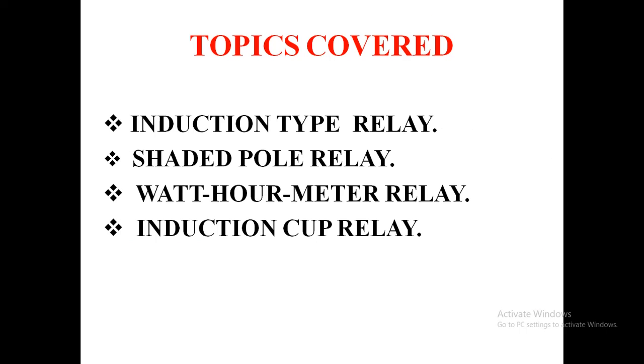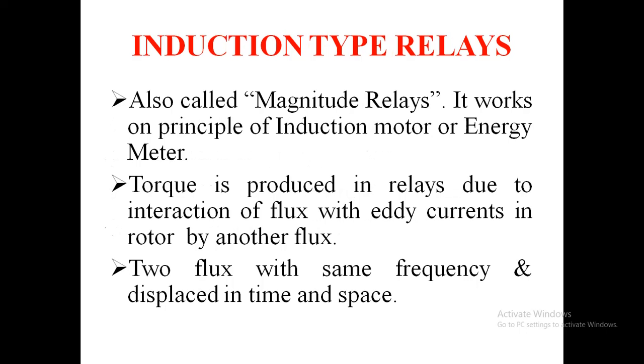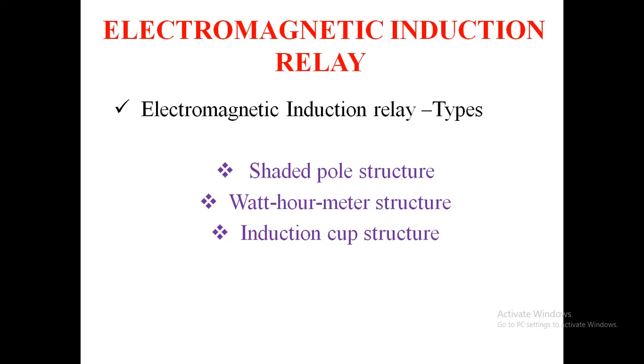These are the topics we are going to cover: the shaded pole relay, watt-meter relay, and induction cup type relay. In this induction type relay, it is also called a magnitude relay, which works on the principle of induction motor or energy meter. The torque produced in this relay is due to the interaction of flux in the rotor by another flux — two fluxes with the same frequency, displaced in time and space.